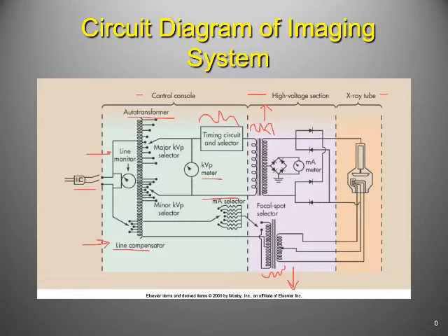And one of the reasons for that, again, is we're stepping down to power the X-ray tube. So this mA selector is going straight into the tube, right? This power here.